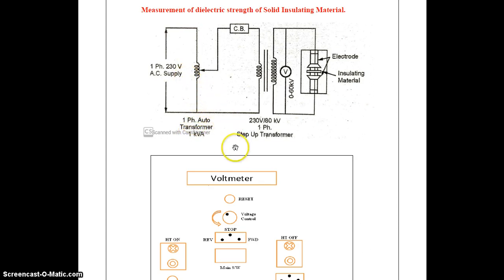is connected to the step up transformer. The input voltage of the step up transformer is 230 volt. It converts it to 80 kilovolt. A step up transformer means the output voltage is greater than the input voltage. Then the secondary winding of the step up transformer is connected to the two electrodes. Then the solid insulating material is placed between the two electrodes. One electrode is called the point electrode, and the other electrode is called the ground electrode.